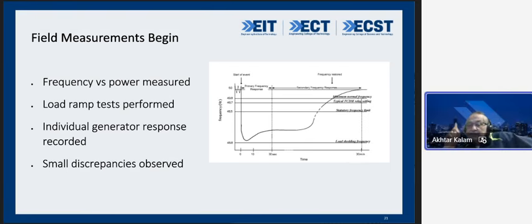If you did dynamic response, you would have seen subtle differences appearing, but if you did static values, you will not get anything. So look at that: you would do frequency versus power. You measured that, performed the load ramp test, looked at individual generator response, recorded all that, and checked for any discrepancies.